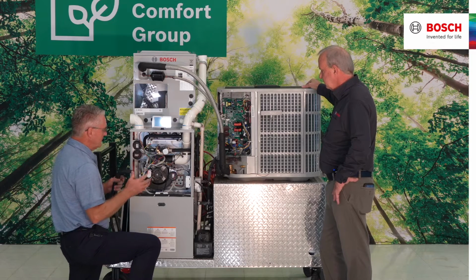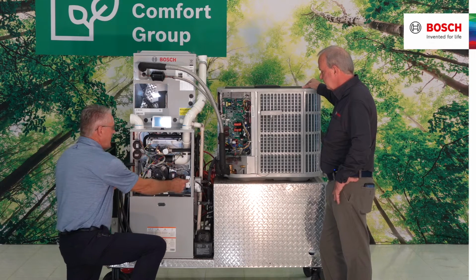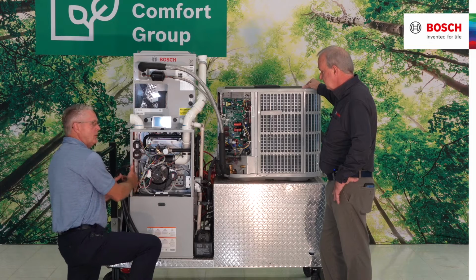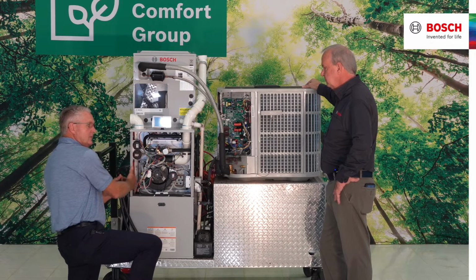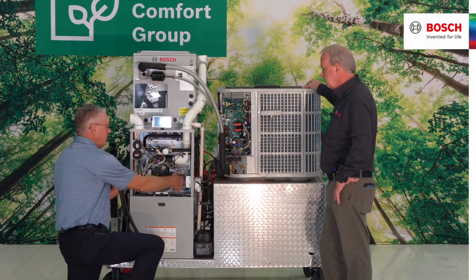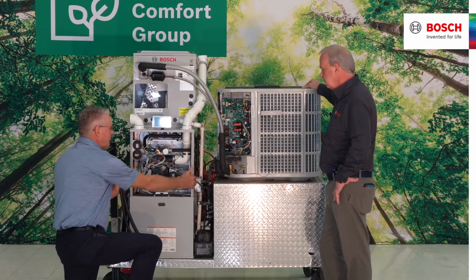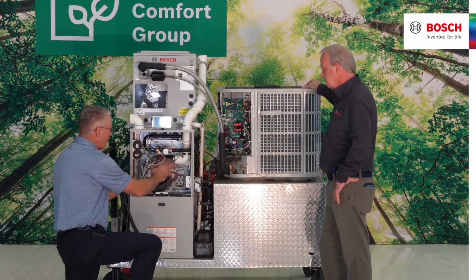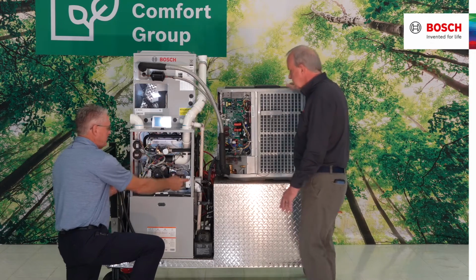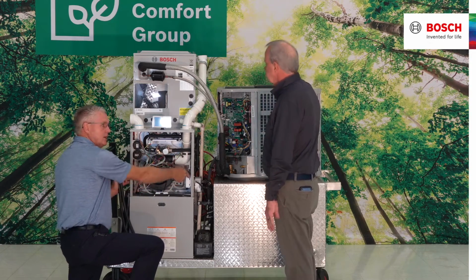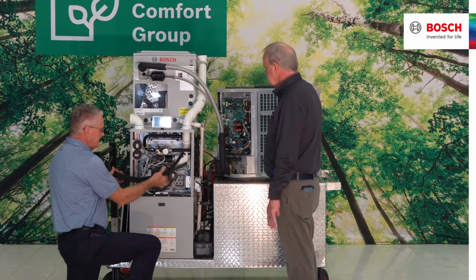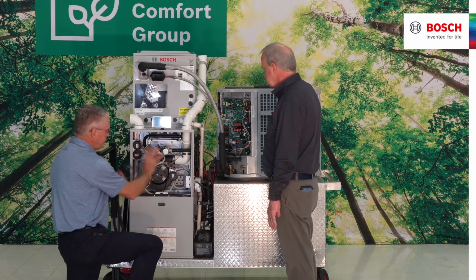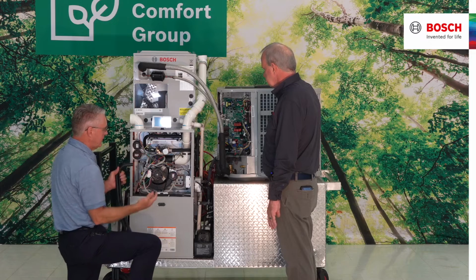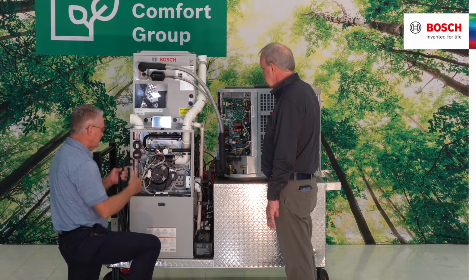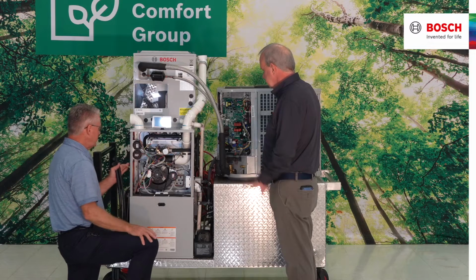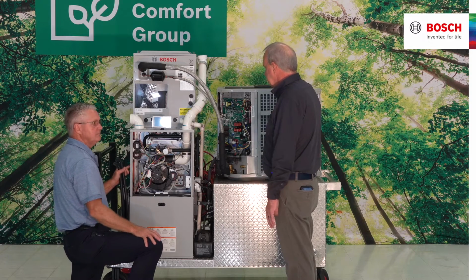The other thing that is really nice about this furnace is that my E-box came over here on the right-hand side, or the left-hand side looking at it, and I moved it over to this side when we set it on this training cart. There were enough wires inside to be able to move the E-box from one side to the other. Same way with this, I've got enough hose. Once you set this up in an application, you're not going to move it, so cutting these hoses once and putting the hose clamps on is going to be good for that application. It's going to be done.